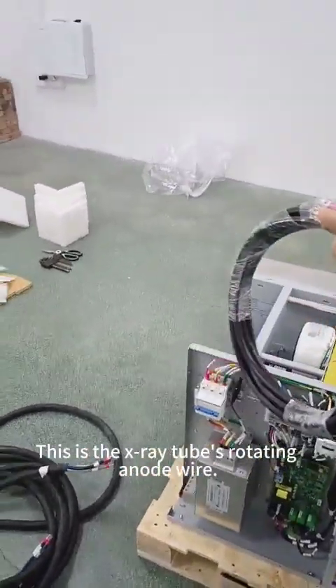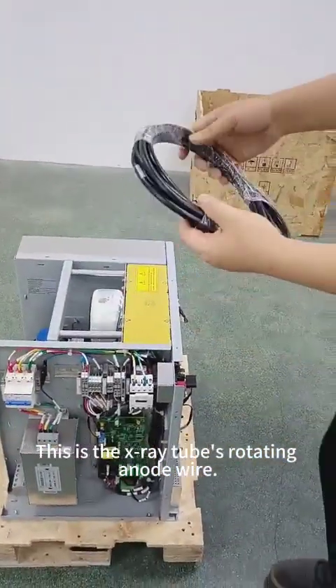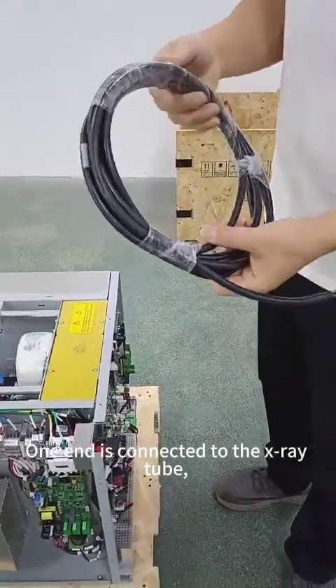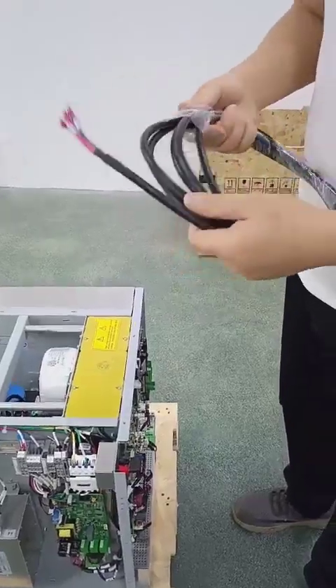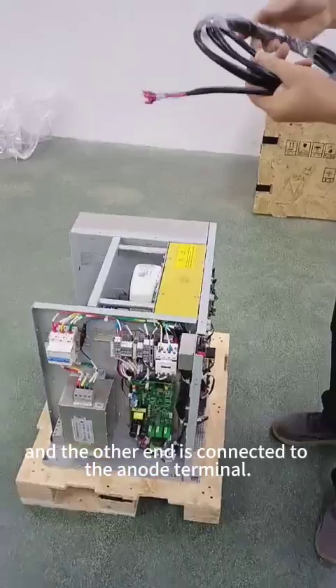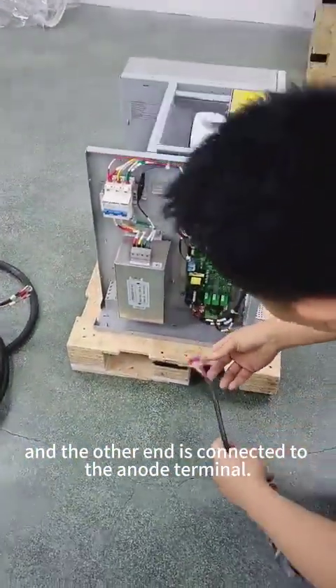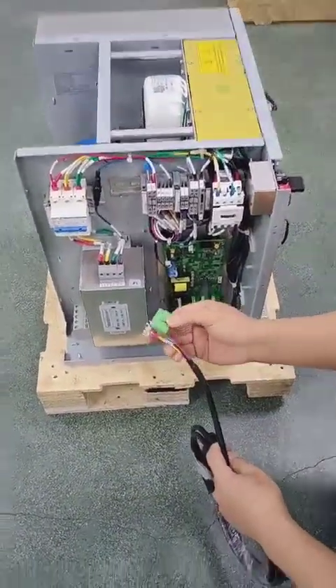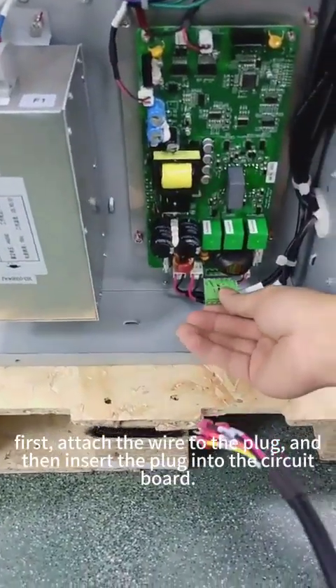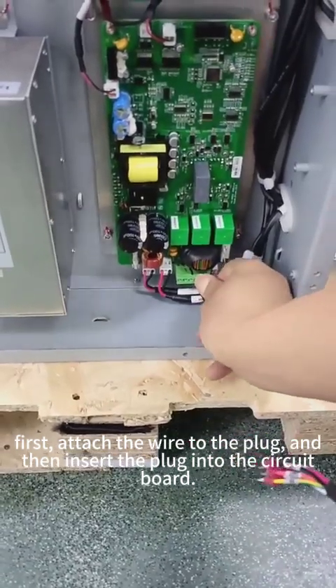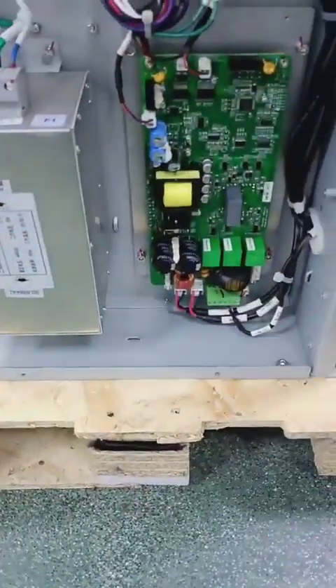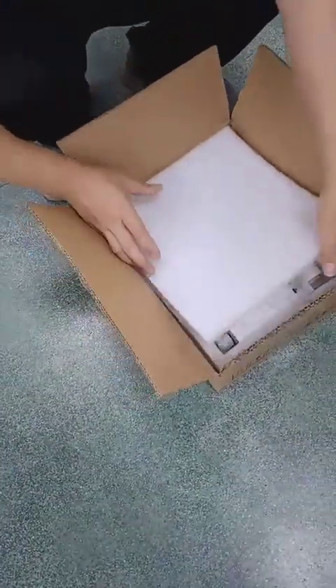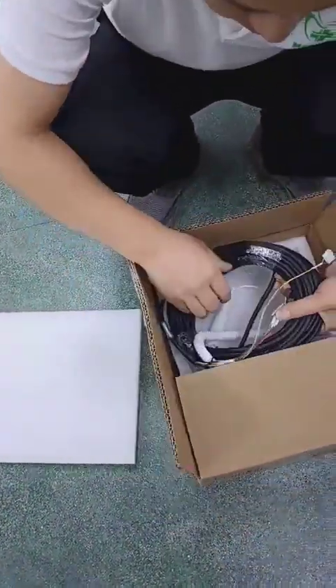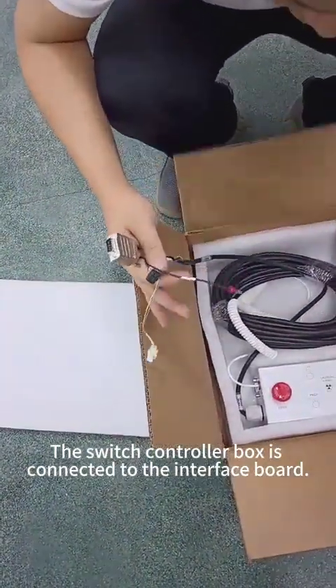This is the X-ray tube's rotating anode wire. One end is connected to the X-ray tube. And the other end is connected to the anode terminal. First, attach the wire to the plug, and then insert the plug into the circuit board. This is the switch controller box. The switch controller box is connected to the interface board.